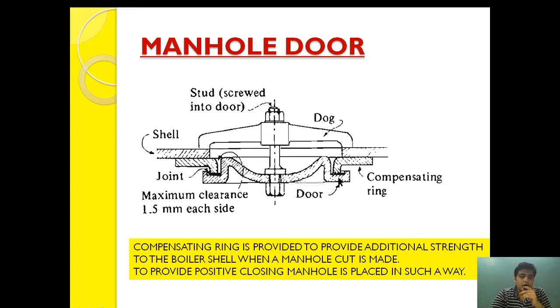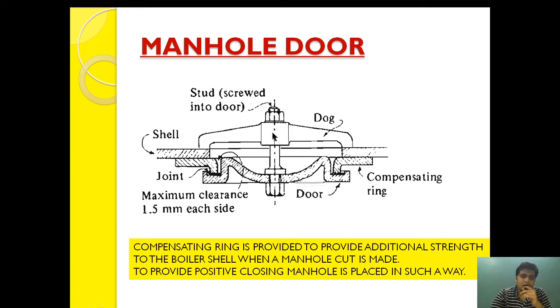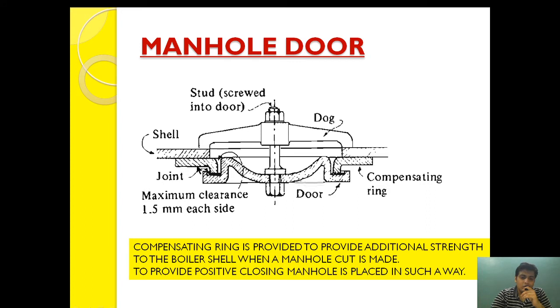As the boiler is a high-temperature working cylindrical vessel, it needs certain clearance for expansion. A clearance of 1.5 is provided on either side to allow thermal expansion. Long studs having good resilience can induce and withstand good stress. The boiler is designed so that the manhole goes from the inward side, and to ensure the strength of the boiler is not lost, the compensating ring is welded to the boiler shell.